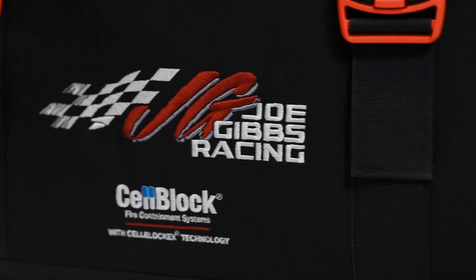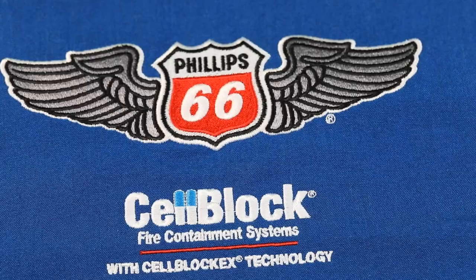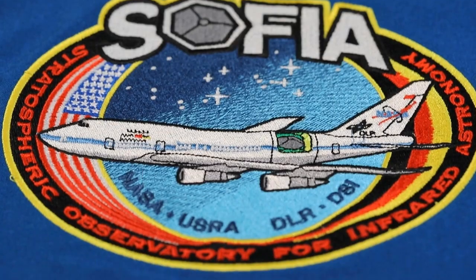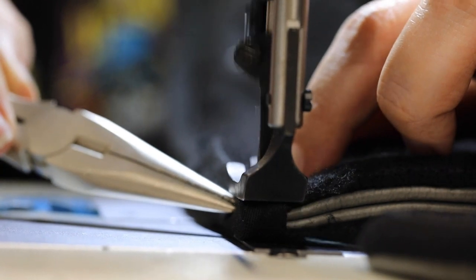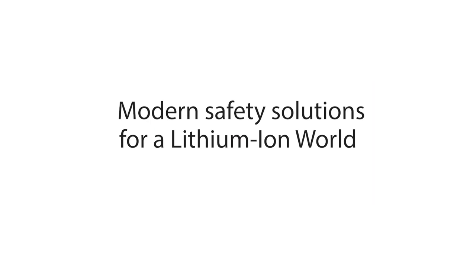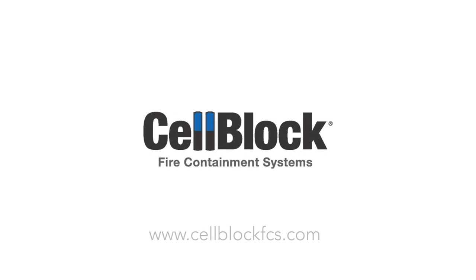Our fire tiles are very important. So this is our other proprietary material. We've developed a heat tile specific to lithium ion battery fire containment that can take an incredible amount of heat. These tiles are currently deployed in our cabinets and in our transportation cases at a half inch thickness. It's a substrate. And that tile at a half inch thickness can take 2000 degrees F in a direct hit, sustained for a half an hour, and you won't get a temperature rise of more than 200 degrees on the backside of the tile. So that's really key into our containment when we're talking about our containment systems.